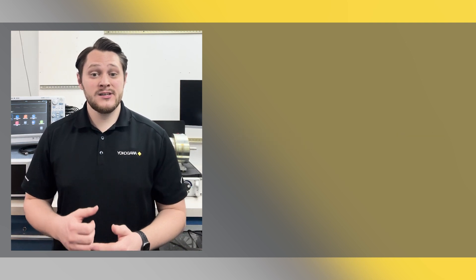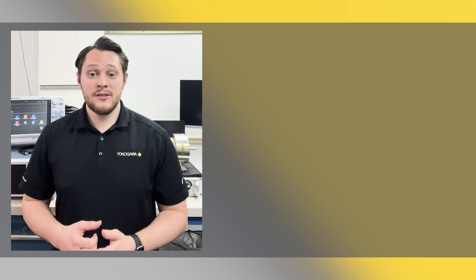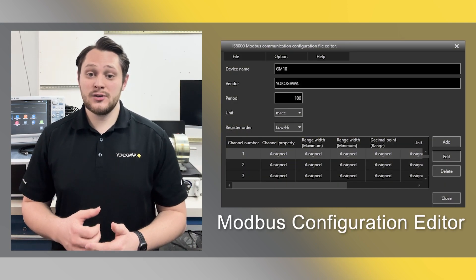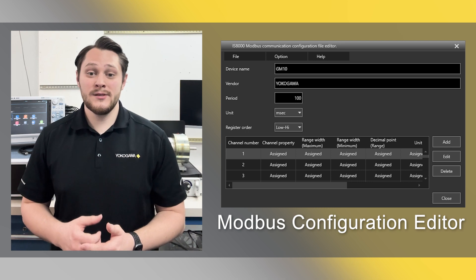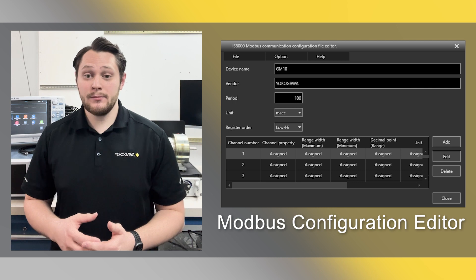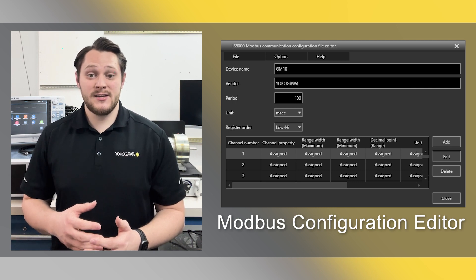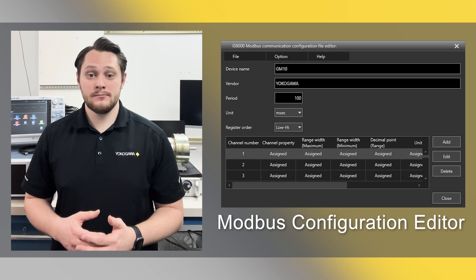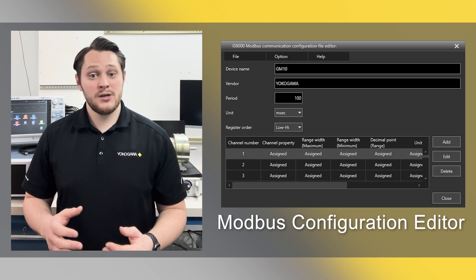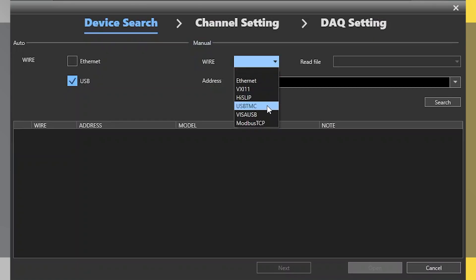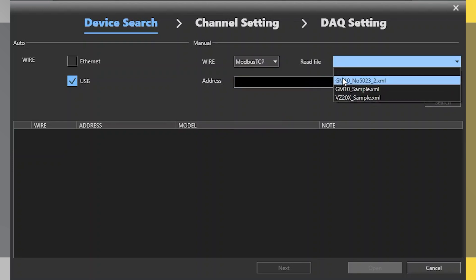The setup for this is actually quite simple. The latest version of IS8000 has a new application to set the registers for Modbus TCP protocols. Once you select and set up these registers, you can save this as a sample file to be loaded when bringing in your instrument. Then, opening up IS8000, you select Modbus TCP as one of the communicating instruments, set up the IP address, and select that saved file.